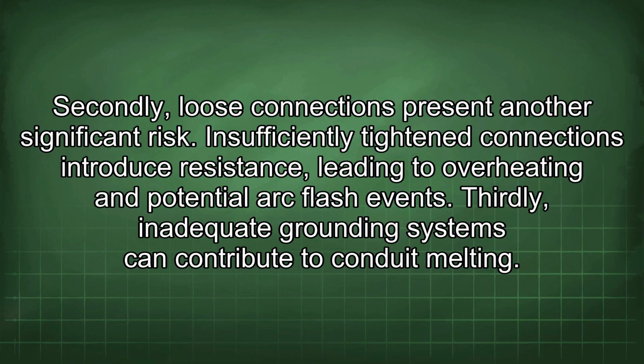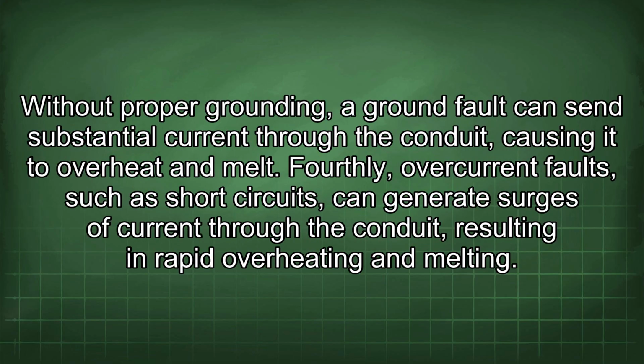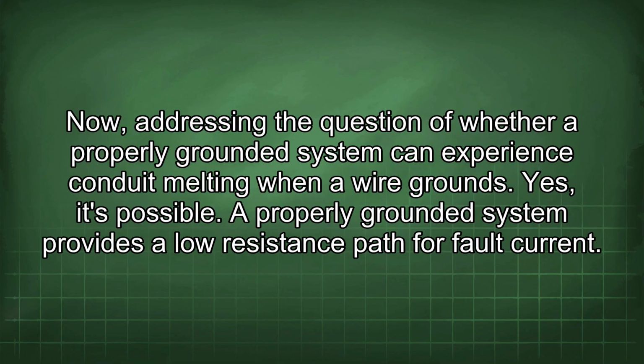Thirdly, inadequate grounding systems can contribute to conduit melting. Without proper grounding, a ground fault can send substantial current through the conduit, causing it to overheat and melt. Fourthly, overcurrent faults such as short circuits can generate surges of current through the conduit, resulting in rapid overheating and melting. Now, addressing the question of whether a properly grounded system can experience conduit melting when a wire grounds.